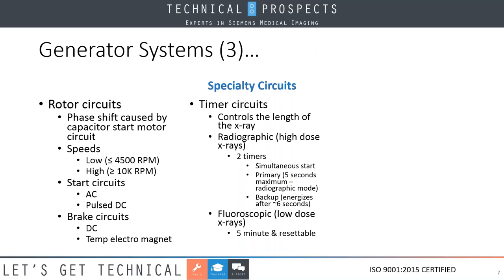A secondary specialty circuit is called a timer circuit. And this is strictly because we don't have a calibrated thumb to control an X-ray. My thumb cannot guarantee me a hundredth, a tenth, a 1.5 second X-ray consistently. So electronically, we've created timer circuits to control the length of the X-ray. What we need to be aware of as field engineers is that on the radiographic side, which is high dose X-rays, there are two timers that will simultaneously start. The primary one is a 5 second maximum in the radiographic mode, and this is regulated by law. The secondary timer, which is known as a backup timer, which must start at the same time, typically energizes after about 6 seconds to terminate the X-ray.